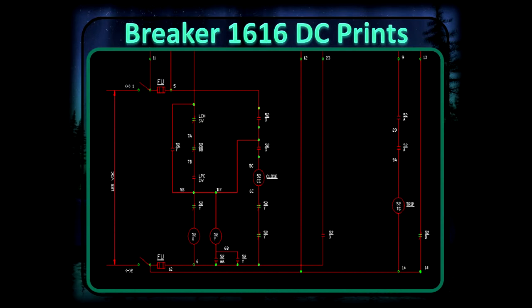So the first thing when you're going to do this test, you have to look at your DC prints, and you have to determine where you're going to put your leads, because every breaker is different. First we're going to look at where our main DC source is, because those are the first leads we're going to hook up on the device.